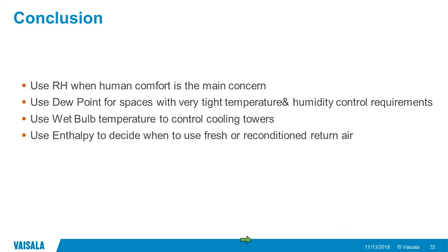For controlling cooling towers and to achieve free cooling, wet bulb is usually the control parameter of choice. But then if you're trying to really optimize your use of outside air and deciding whether to recondition return air or take in more or less outside air, then actually enthalpy is the right parameter that will tell you directly what to do.